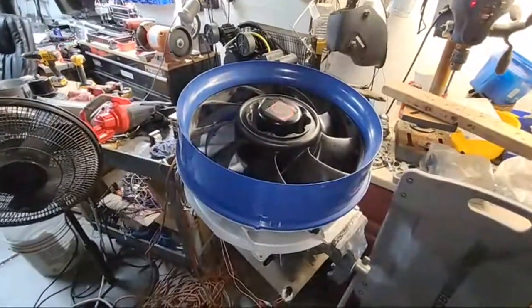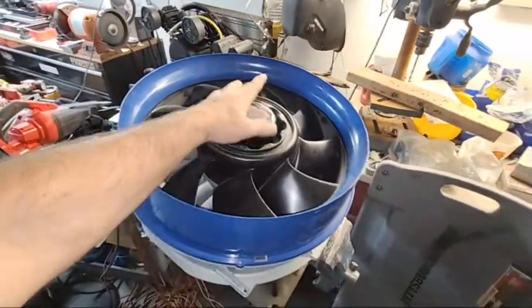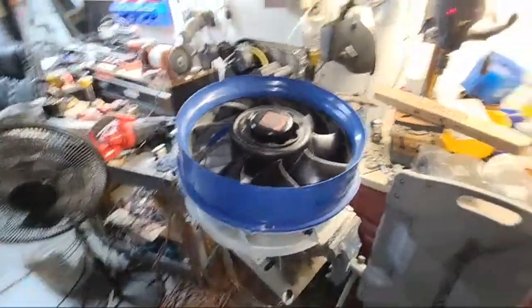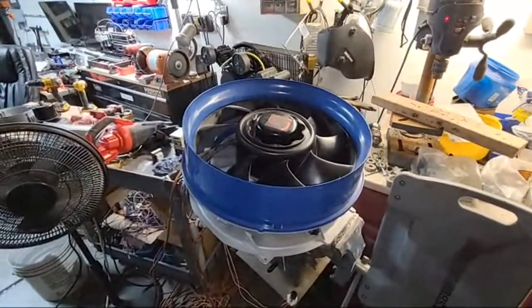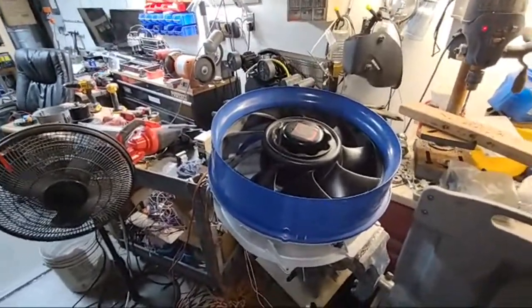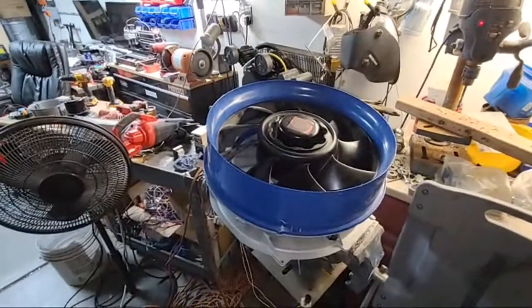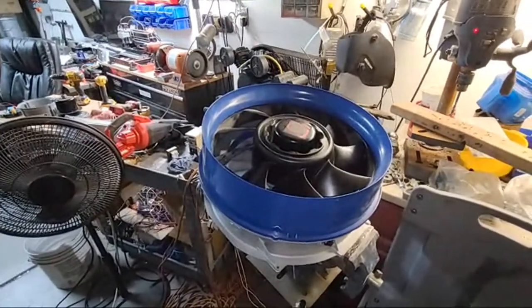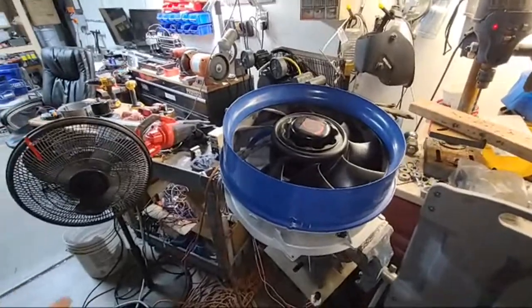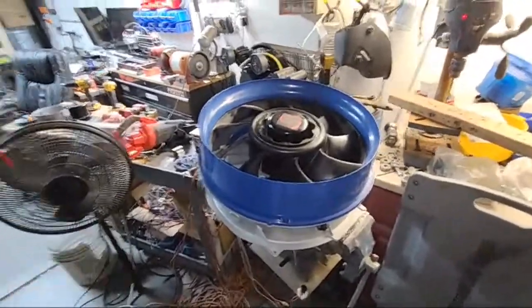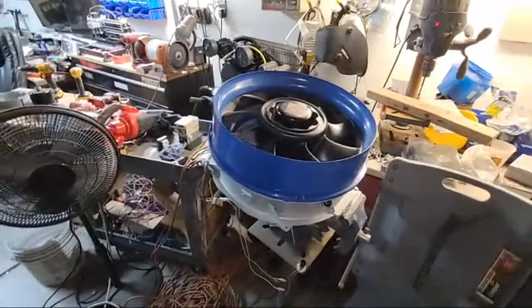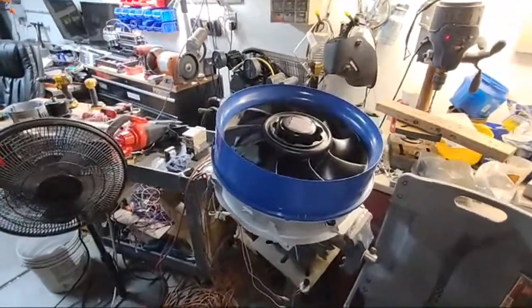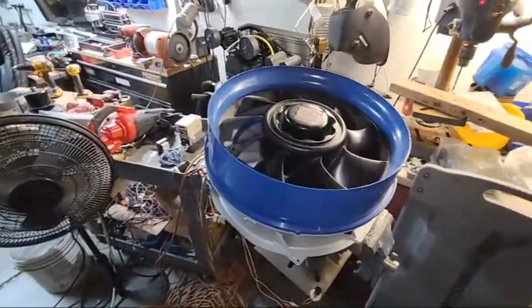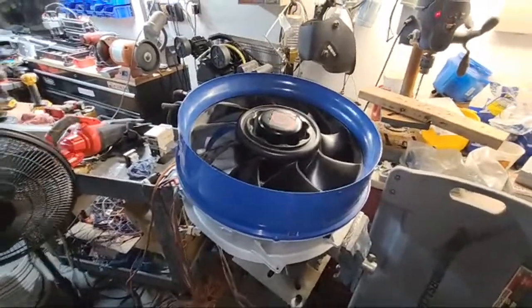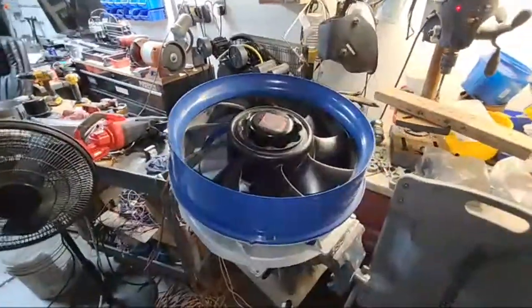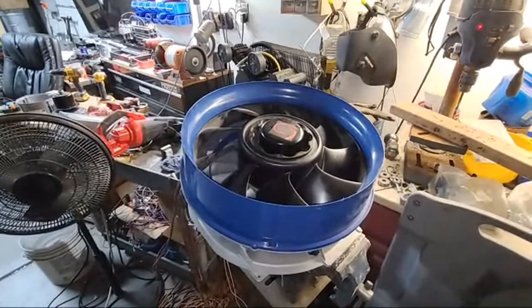And then once we did, I pulled that charge out. Once he knew he had other ones, he wrote down the numbers. I went to every one of those units and pulled out 4 or 5 ounces out of the same couple of models, and didn't even look. I just kept the hose connected to the scale and went and pulled it out of every one of the ones that was tripping on his EMS. And then we didn't have a problem after that. Didn't lose the split temperatures or anything. Just from the factory, slightly overcharged. Kind of weird for a water source heat pump.